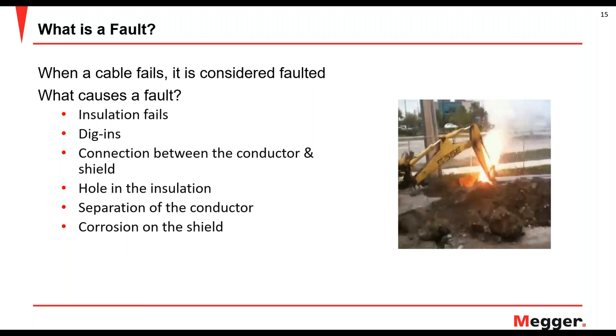Going over to faults — when a cable fails, it's considered faulted. What causes the fault? It could be anything: insulation failure from transient overvoltages, a dig-in like an excavator, a physical short between the conductor and the shield where they're physically touching, a pinhole in the insulation, or a complete separation of the conductor — meaning a high fault current physically melted an aluminum cable in two. It could also be corrosion in the shield, where the unjacketed concentric neutral corroded over time where it's no longer viable and you have an open on the concentric neutral or shield.